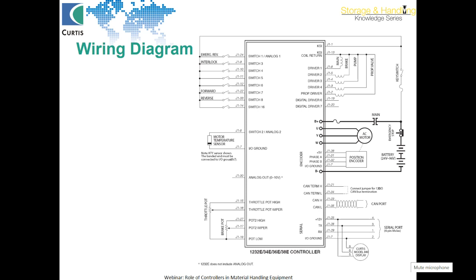Vehicle safety functions we will talk about. Controller employs a dual microprocessor design, which means there is a primary microprocessor and there is a secondary microprocessor. Secondary microprocessor is also called supervisory microprocessor. So it continuously keeps watch on all the functions of the controller, whether everything is going as desired. In case of any faults outside or inside the controller, it will alert the main microprocessor, in addition to main microprocessor's own tracking of the faults. In case of any rare failure with the main microprocessor, the supervisory microprocessor will take control of the vehicle and ensure a fail-safe shutdown.